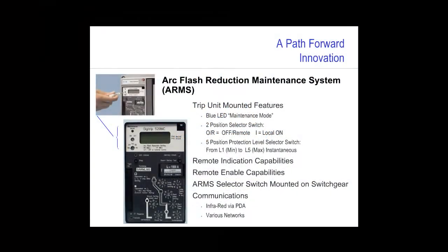Finally, let's take a look at a third innovation area, an area surrounding technology and protective relaying itself. A number of the higher-end digital protective relays today will include multiple settings group capability, essentially allowing the operator to set one selective coordination curve for one situation and a second for another.